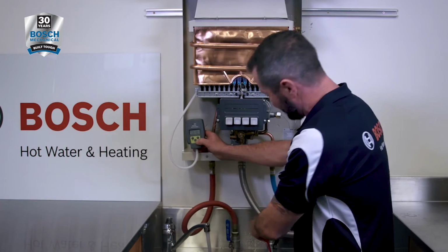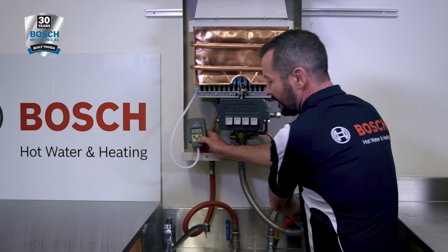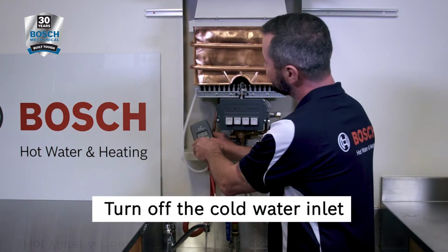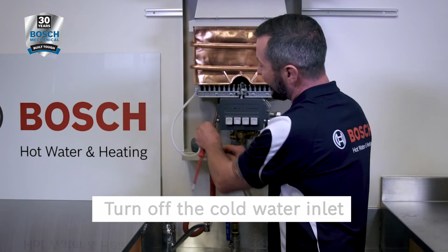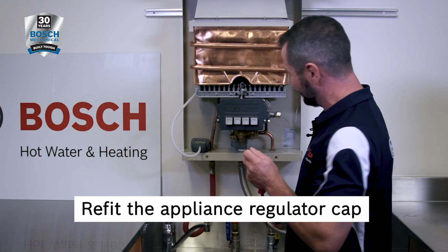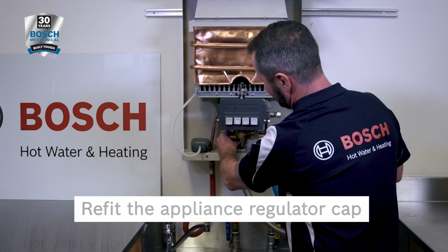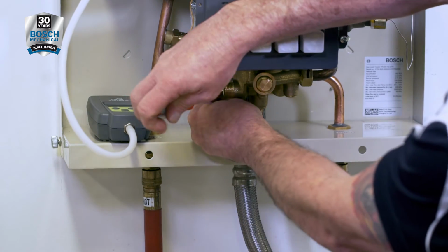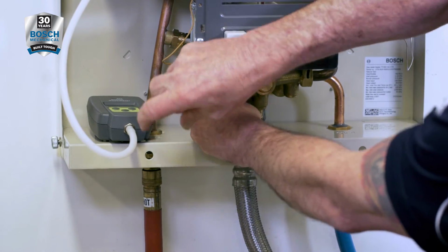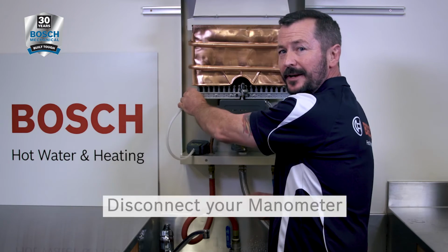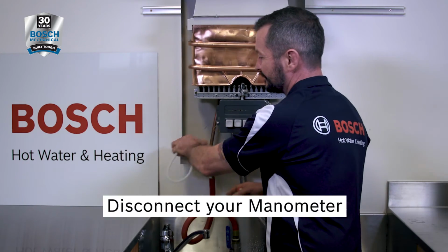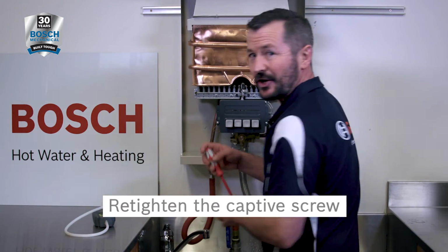Once the pressure is set, turn off the cold water inlet and refit the cap on the appliance regulator. Disconnect your manometer and tighten the captive screw.